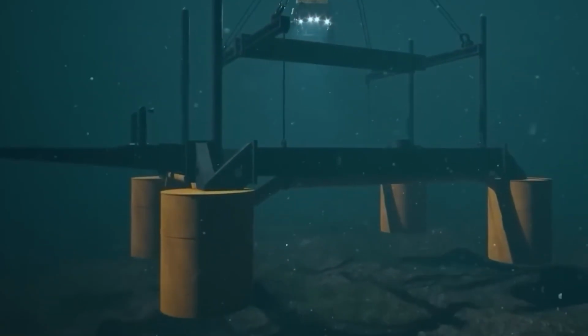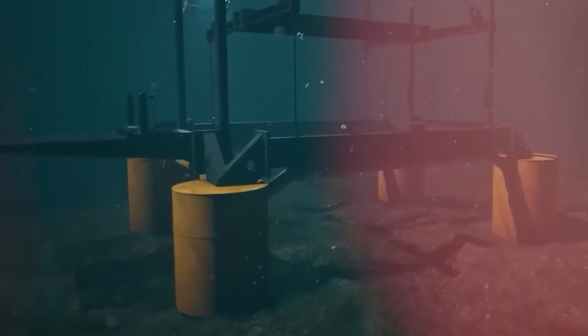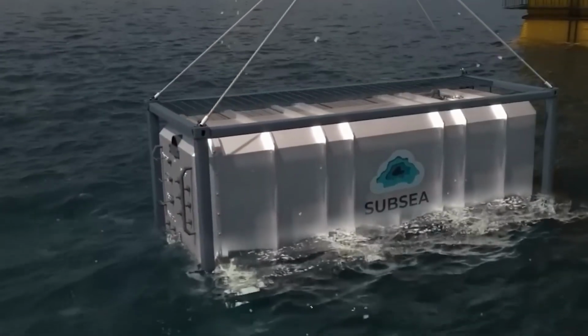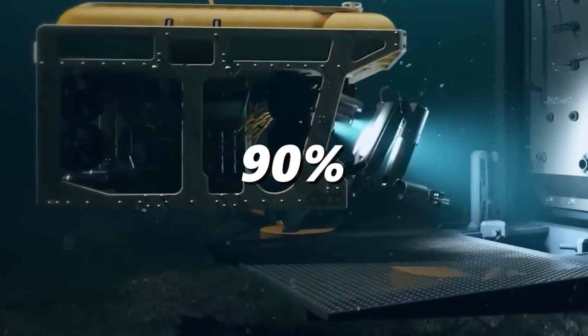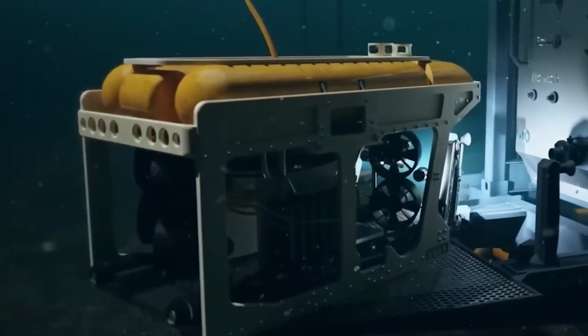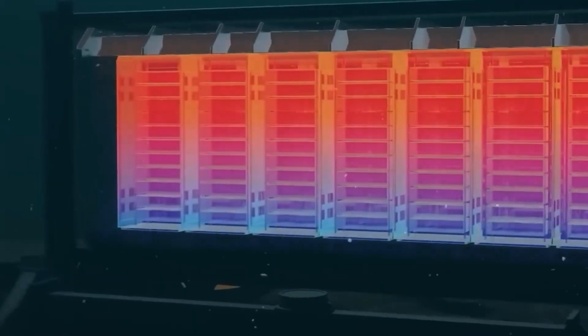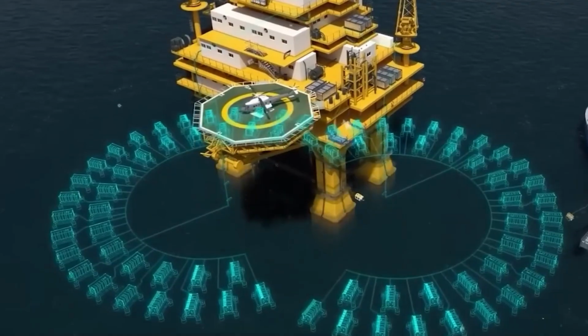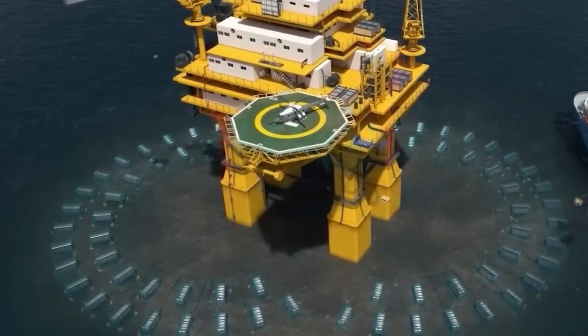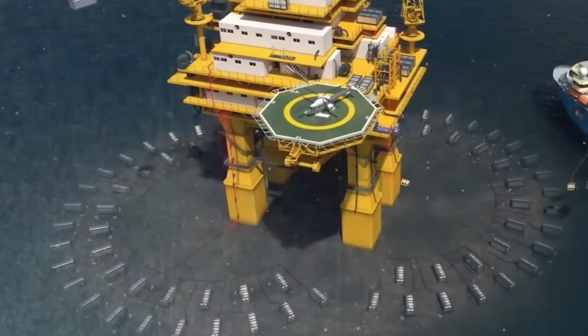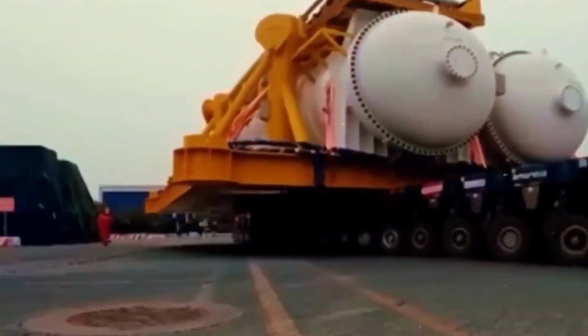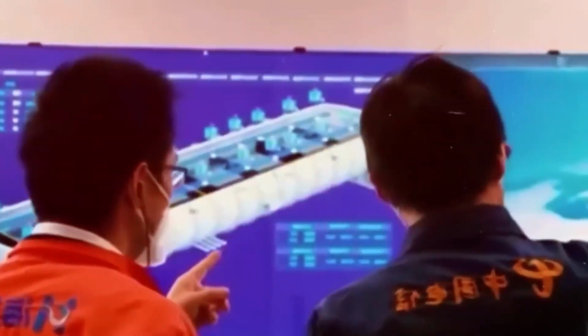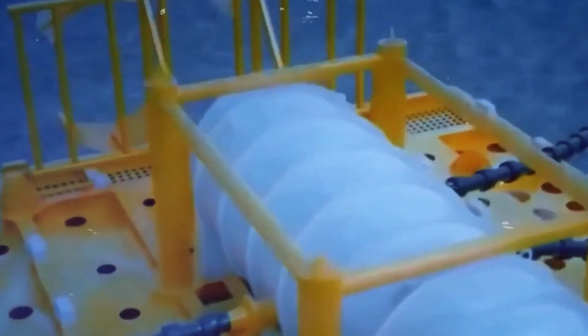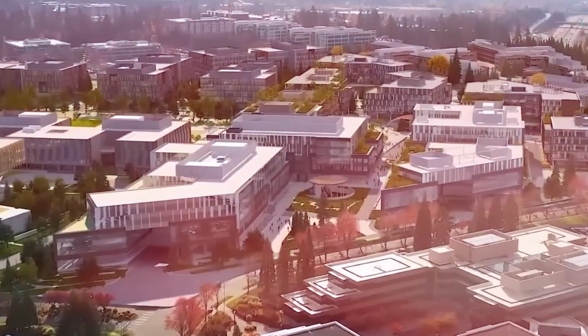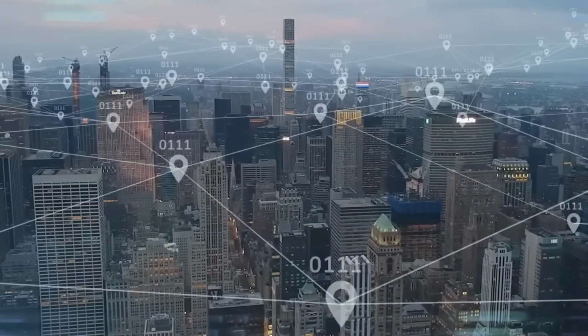It also essentially eliminates freshwater consumption entirely and cuts land use for the facility by more than 90% compared to a traditional data center with equivalent capacity. Put bluntly, this is a data center that barely touches the freshwater supply, barely touches the power grid beyond its own dedicated wind farm, and barely touches the land at all. That's 3 of the biggest political and environmental headaches in modern data center construction, addressed simultaneously by putting the whole problem underwater.